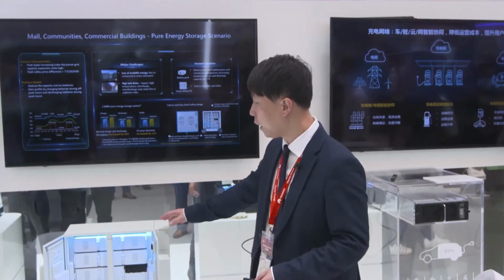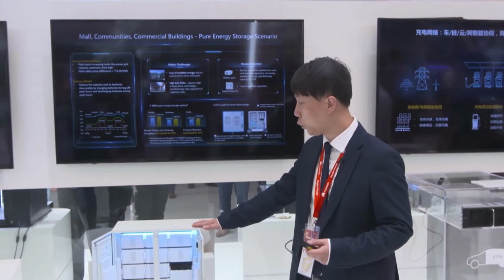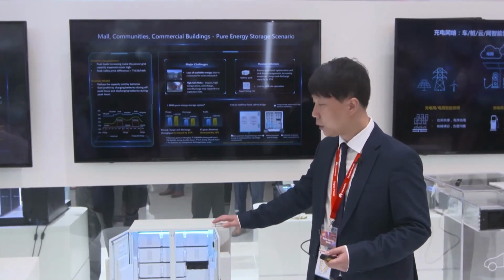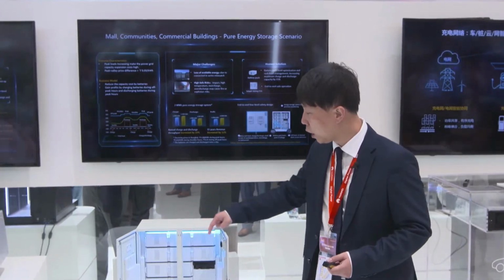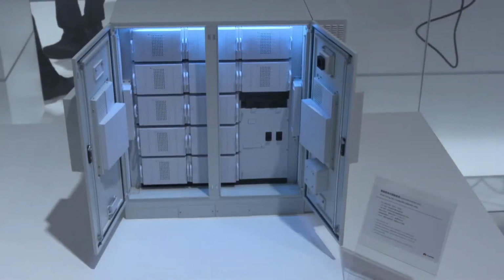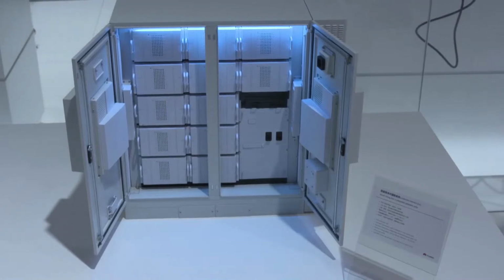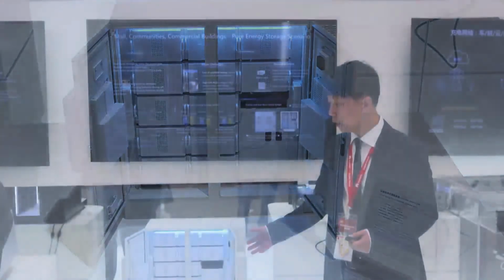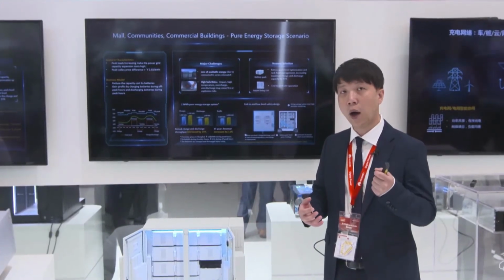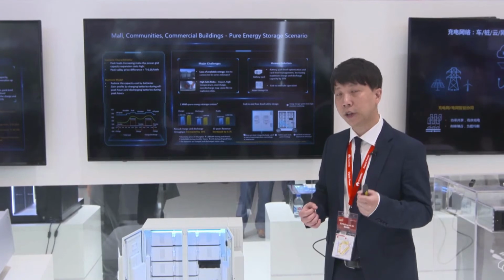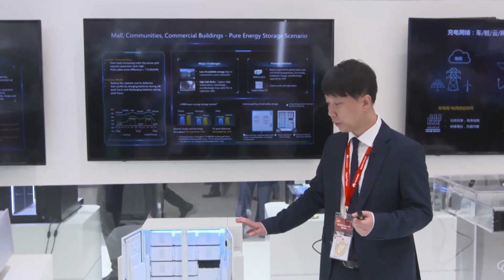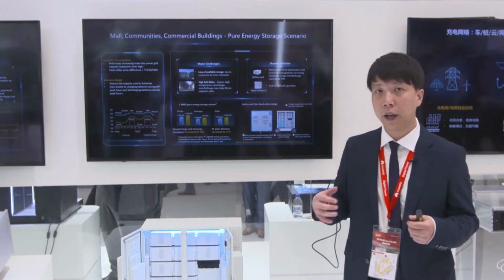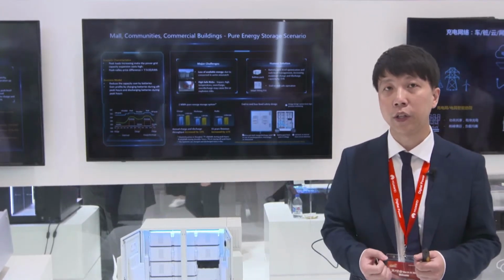And here is a model of our 200 kilowatt hour system. You can see this consists of 12 battery modules, and the total capacity of this is 200 kilowatt hours. And also within this cabinet, there's a rack management system. So the structure is unique. There's one pack optimization and one rack management structure, to improve our yield, to improve the usable energy of the storage by 15%.